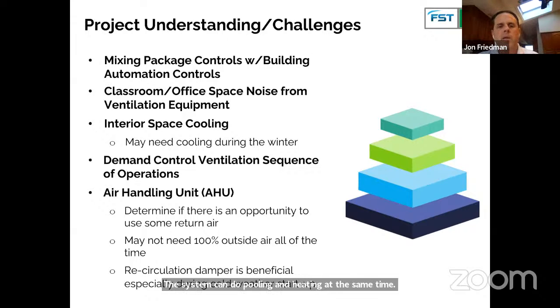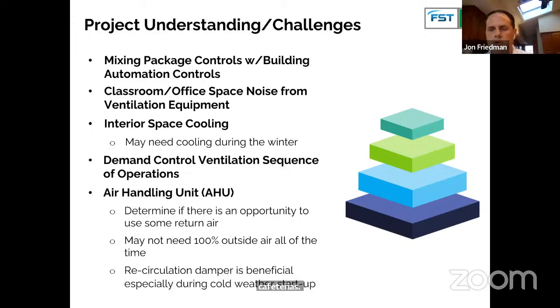The demand control ventilation sequence comes into play, like I was talking about for the gyms and the auditoriums and the cafeterias. If there's no one in those rooms or very few people, you don't need to be pumping in thousands and tens of thousands of CFM of airflow. It's just very inefficient. There are sequences to avoid that, which will translate into significant energy savings.